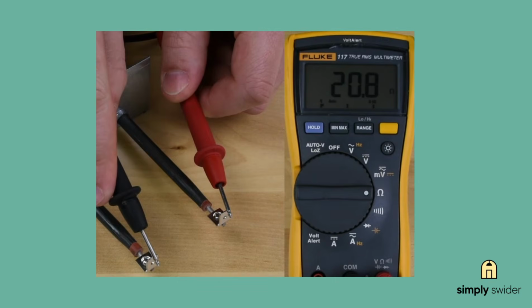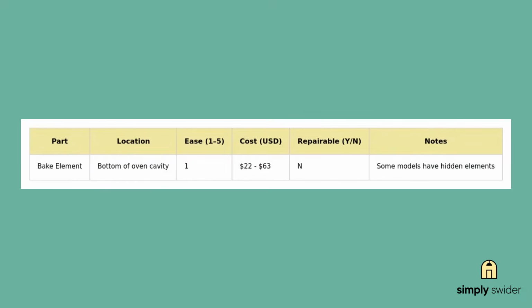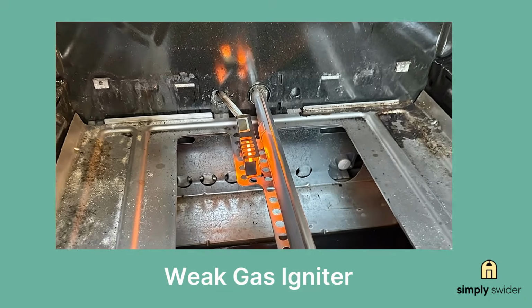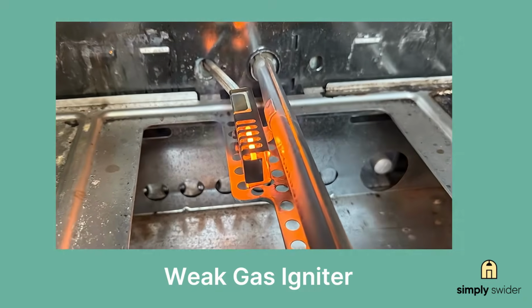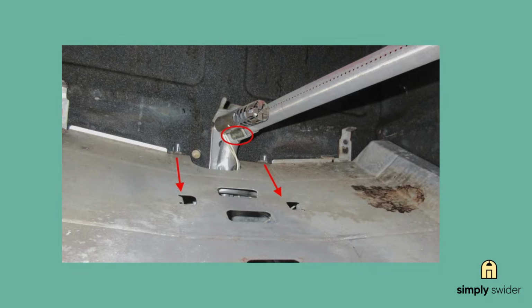Here's something that catches people off guard. Some models have hidden elements under a metal cover, so you might need to remove a couple screws to actually see what's going on. You'll notice the igniter glowing bright orange or red, but the burner never actually lights up. You might even smell a little gas, which means gas is trying to come through, but there's no ignition happening. What's happening here is that the silicon carbide igniter has degraded over time. It still glows, but it's not drawing enough amperage to open that safety valve.